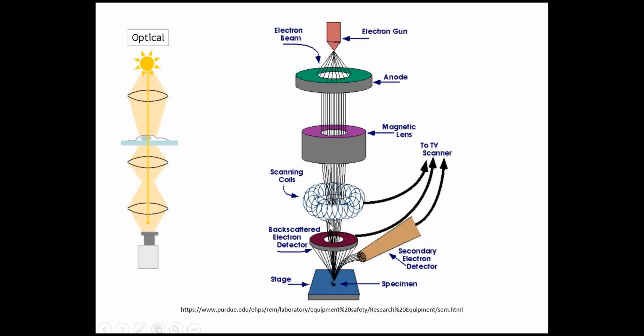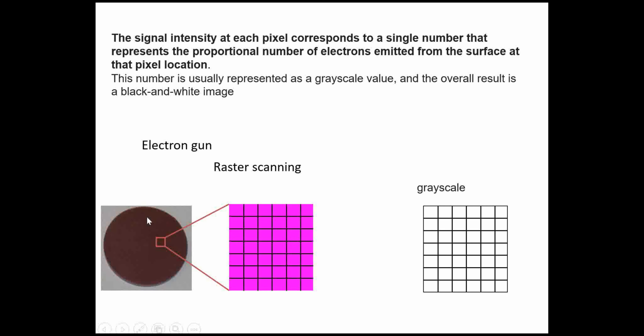The electron beam collides with the sample, generating backscattered and secondary electrons. Secondary electrons are collected by one detector and backscattered electrons by another, and these are used to generate images. The electron gun focuses on each pixel of the sample to get information, then moves to different pixels in a raster pattern. The signal intensity at each pixel corresponds to the number of electrons emitted, represented as a gray value, producing an overall black-and-white image in SEM.